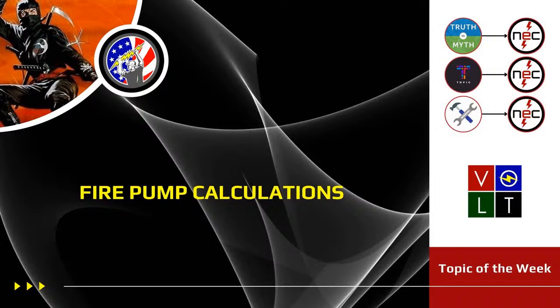This fire pump calculation one is literally one of the only sections in the code where voltage drop is required. So a lot of people get confused on that. They go off, I think it's 210.19, 210.20. Well, it depends on if you're doing it for a branch circuit or feeder. Yeah, but you go in there and it'll say that you either have to be 3% or 5%, or 3% and 5% combined, but that's not a requirement per the NEC. All that is an informational note. Right. So a lot of people don't realize that.